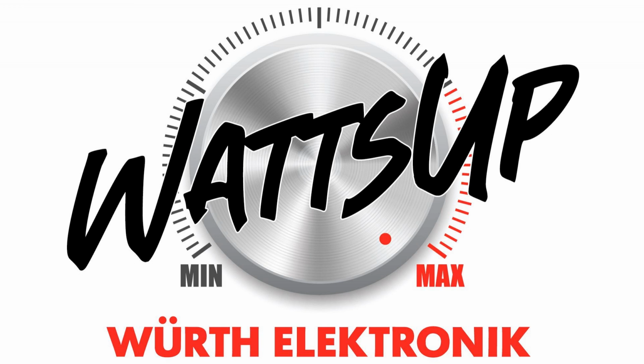I should do what should really be done: design a filter, use the filter kit of Würth, and really solve your problem. So for instance, I go in clear and bright, and I do the modal measurement with the common mode. I open another tab, differential mode, the quasi peak. Now I put the configuration again without the filter. So I have the noise here, the total noise. I'm freezing this one as I did before. I open 2 more and I measure the same.